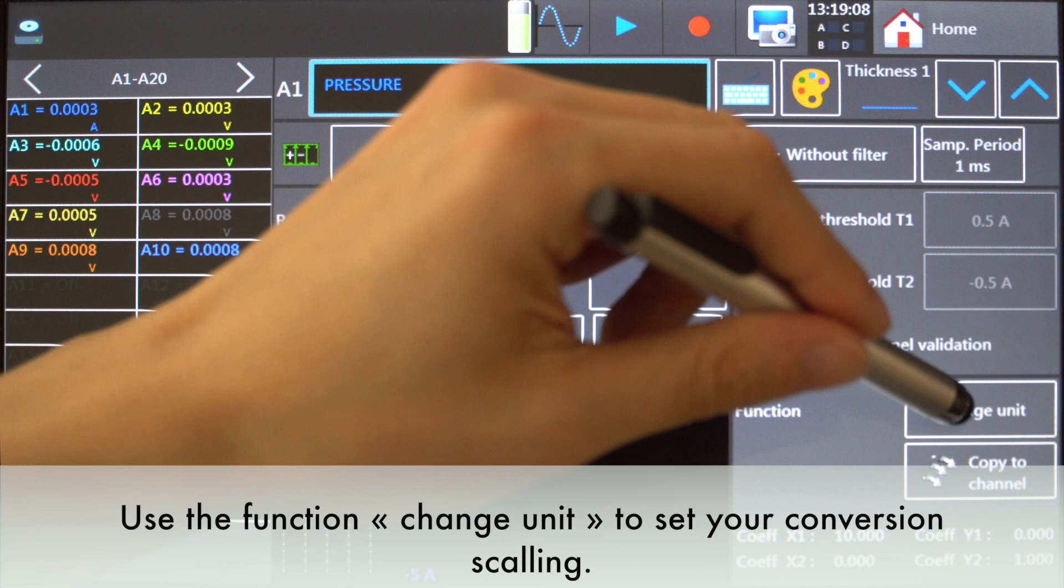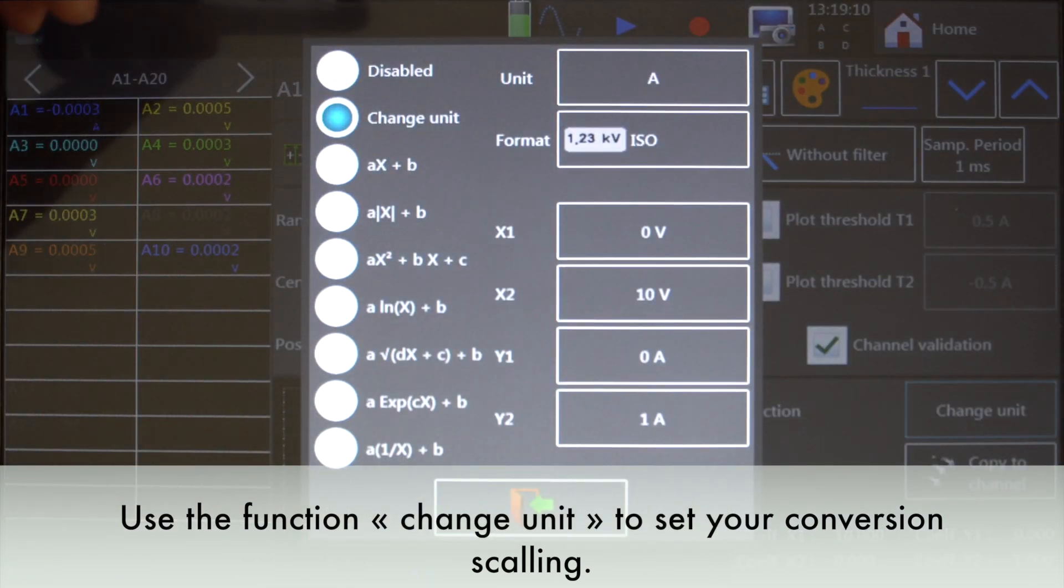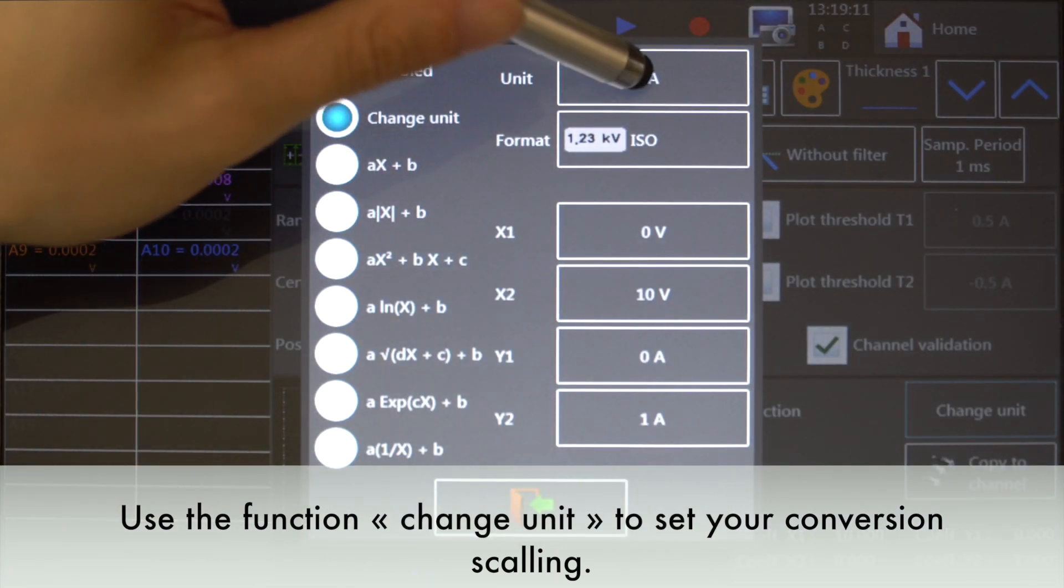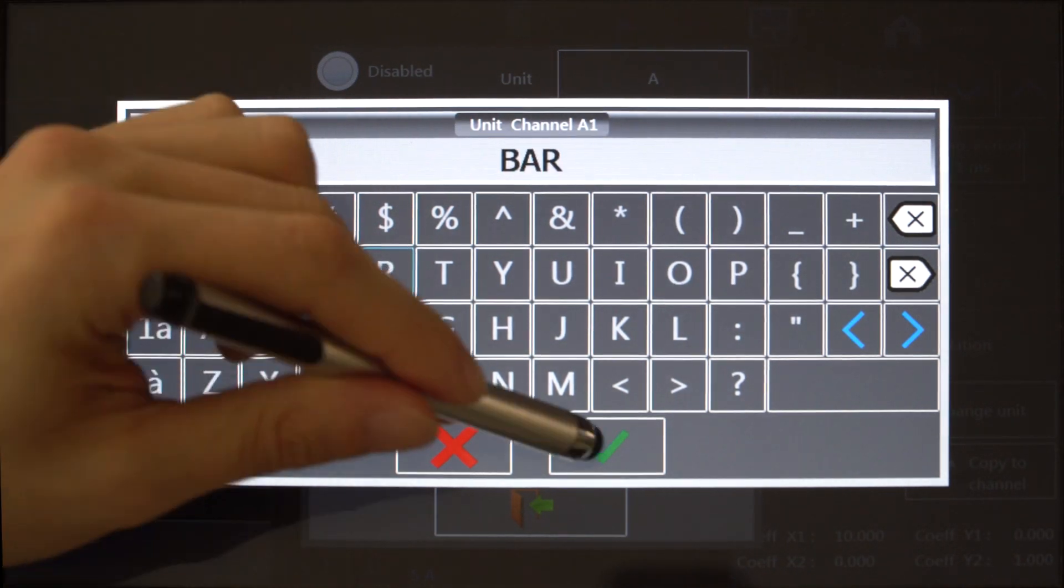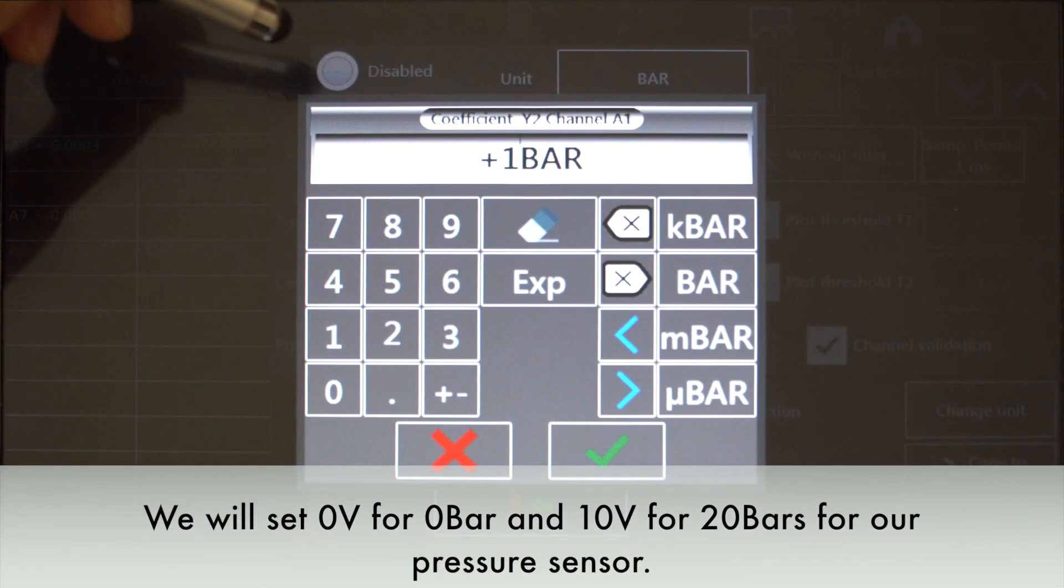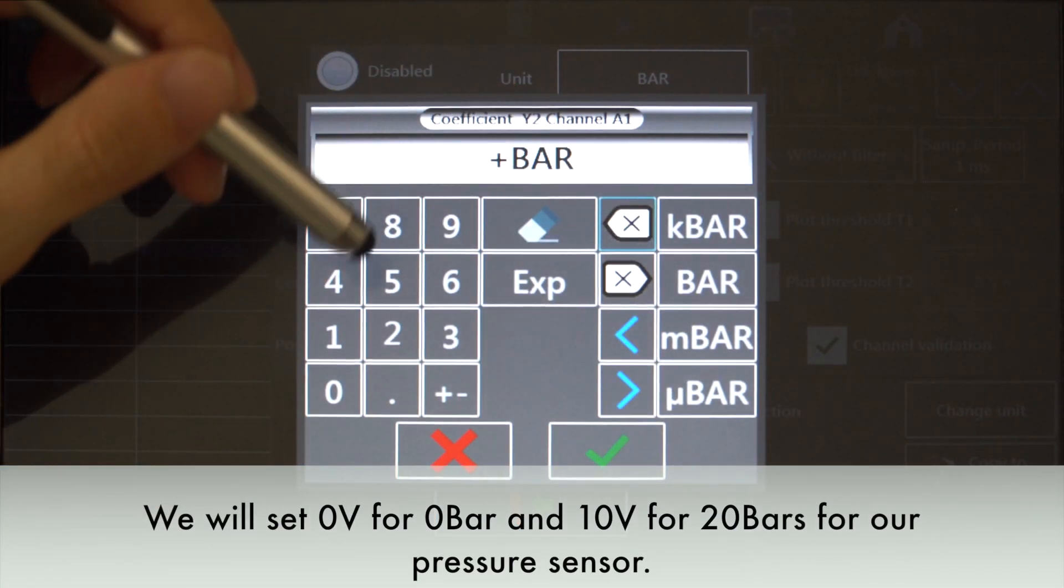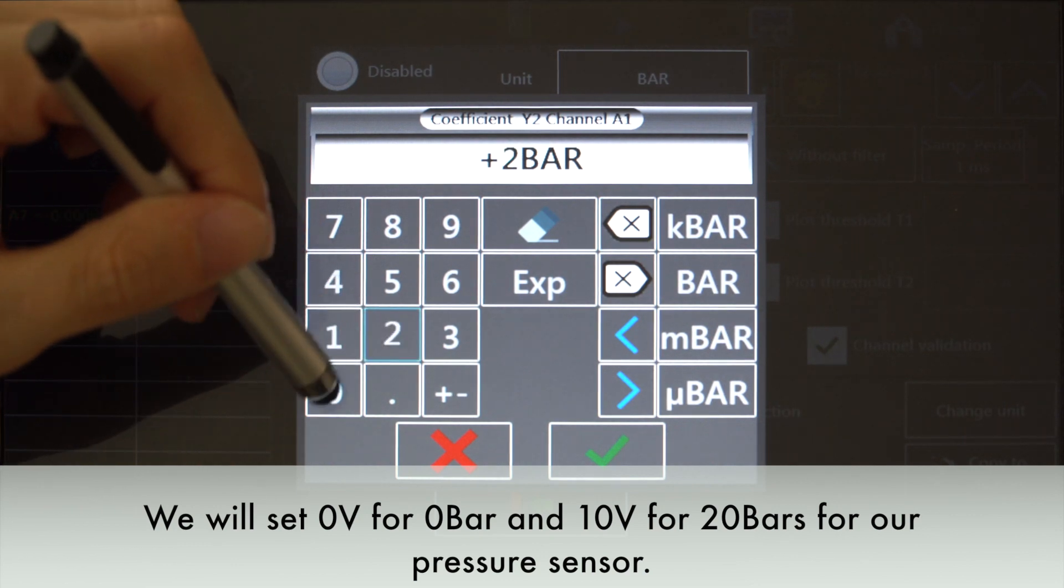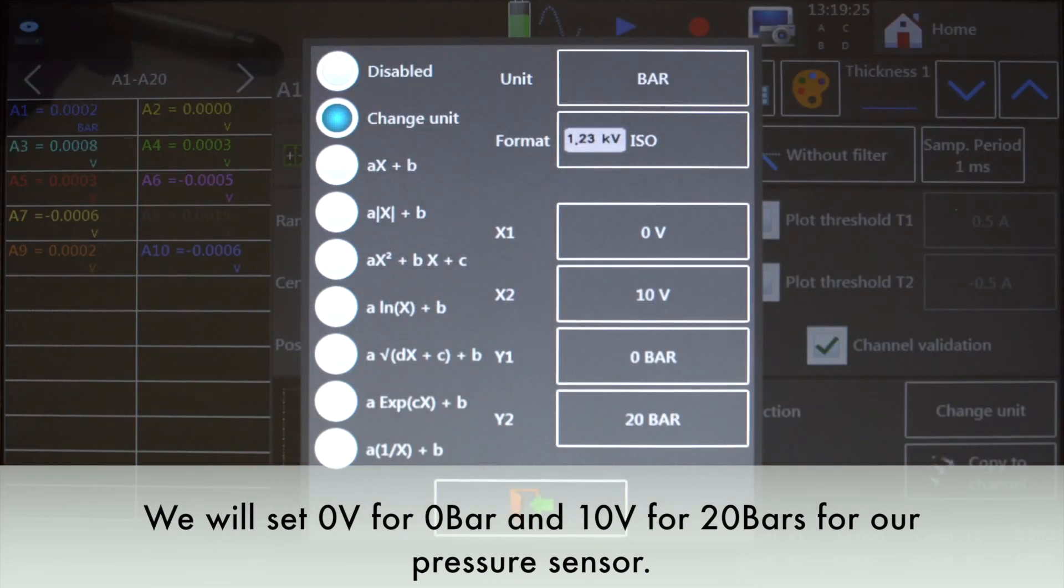Use the function change unit to set your scaling. We will set 0V for 0 bar and 10V for 20 bars for our pressure sensor.